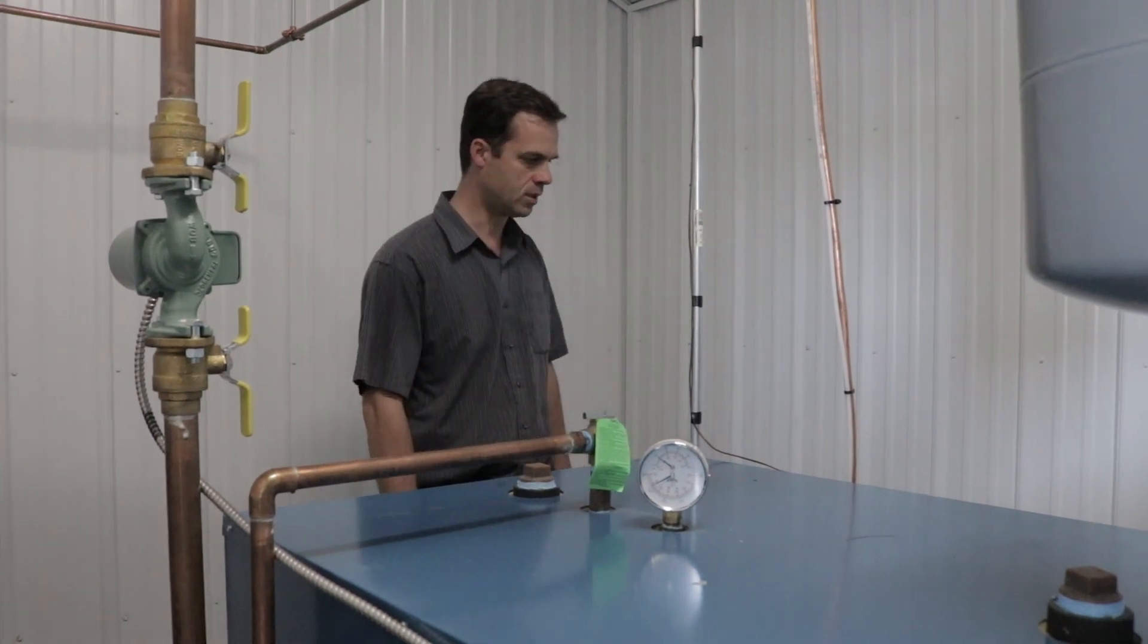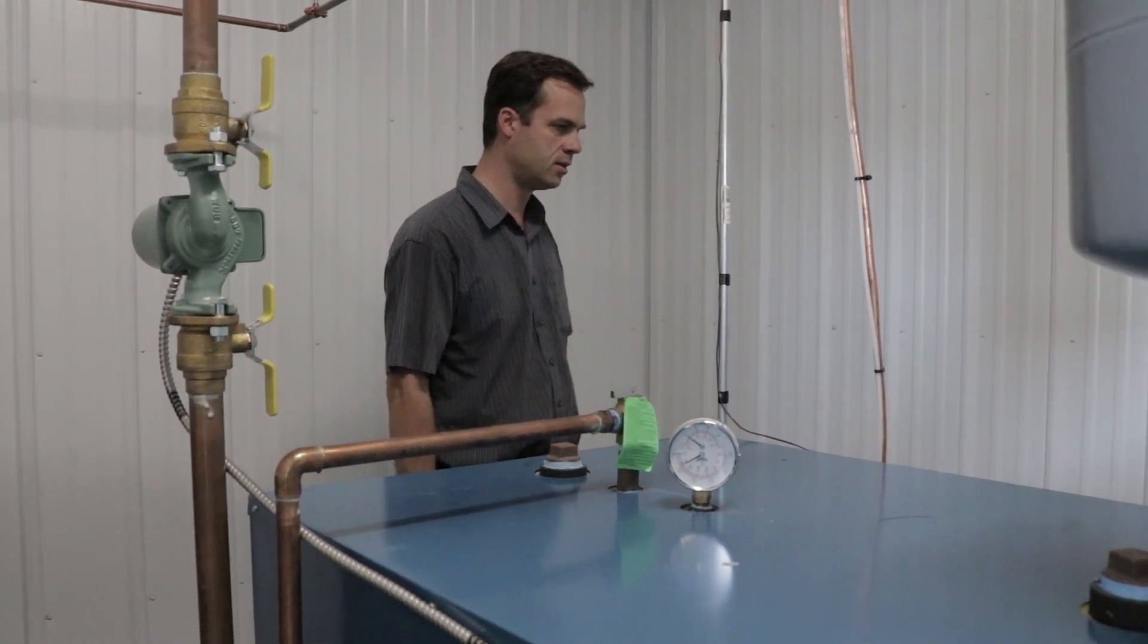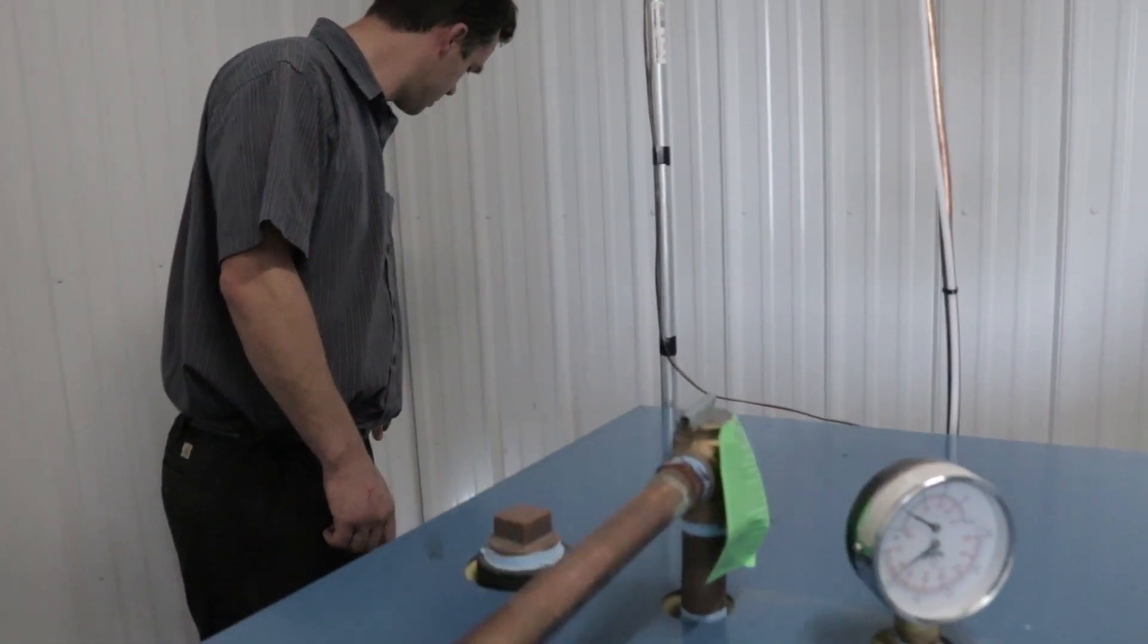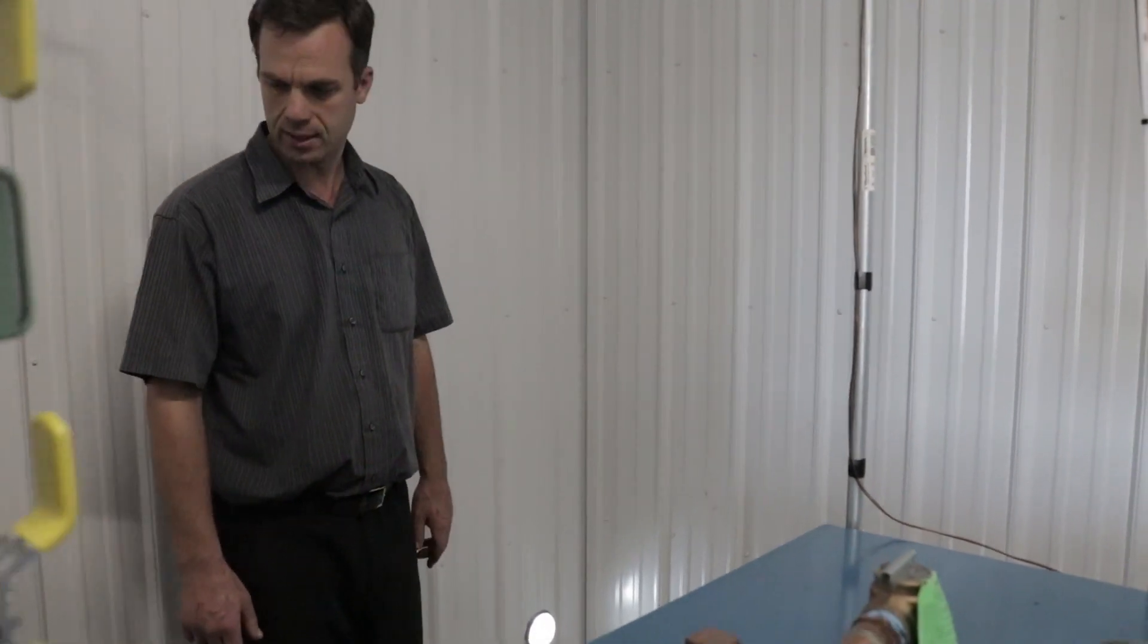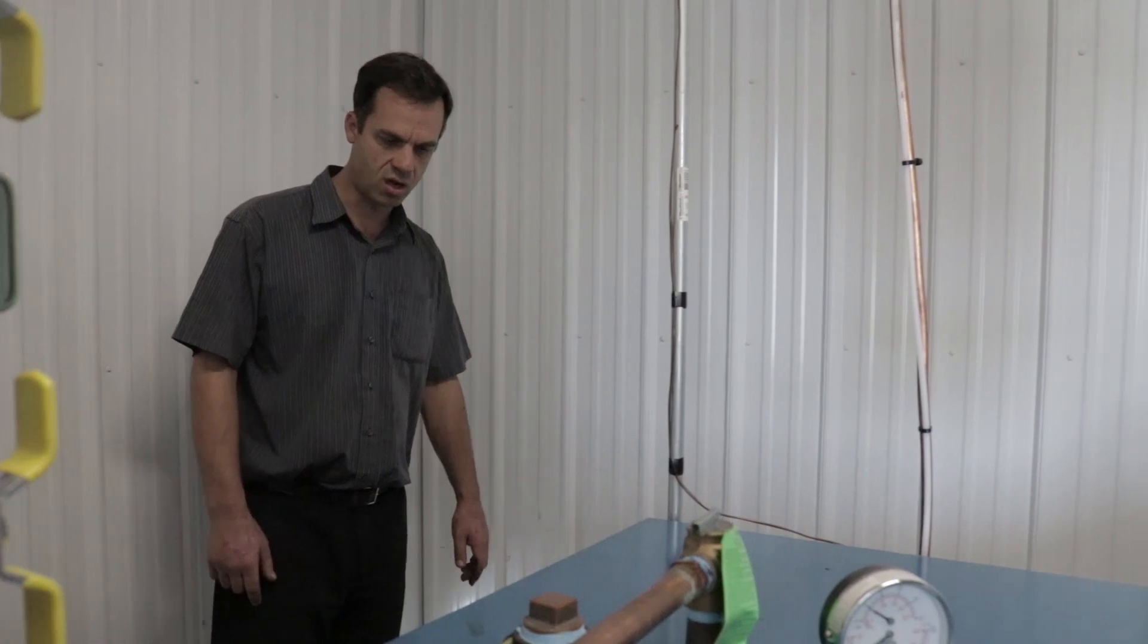In your mechanical room, you must bring in air exchange. There's an air exchange port right here, so that fresh air can come in that the burner is taking away in the combustion process. That's very important that the furnace room is not sealed up tight.